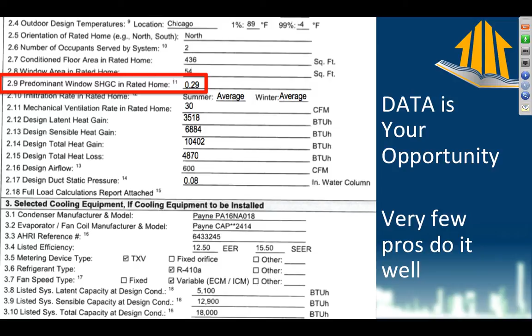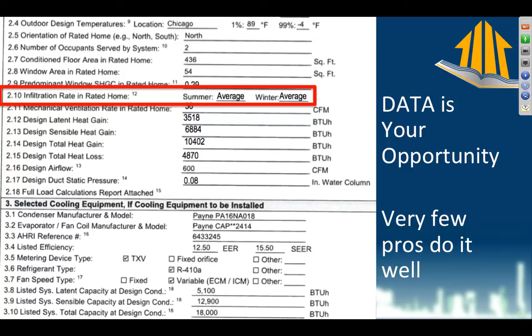Now, the infiltration rate, this is something that's very, very sneaky. And this is why this is a huge opportunity for you who are watching this webinar or watching the recording of it later. What this mechanical engineer put into these fields is average. Now, what in the world does that mean? You don't know. I don't know. The mechanical engineer sure doesn't know. They just put that in there because, I don't know, something. Let's put the average in there because I have no idea what's going on. That is wrong. Those two values are way, way off what this place is actually going to perform like. And that's a problem because now we're going to start oversizing all of the equipment that's needed for this.